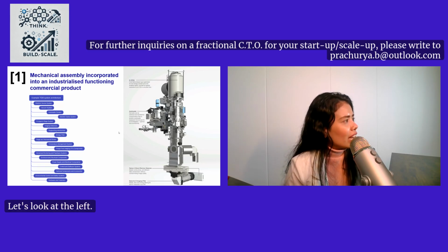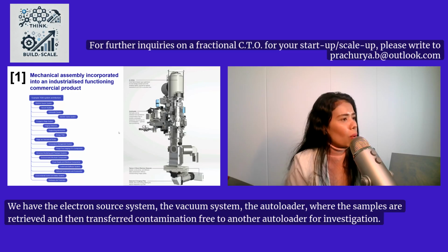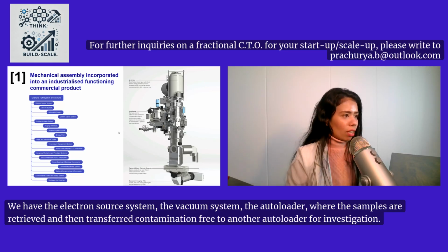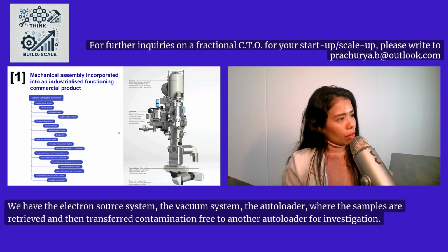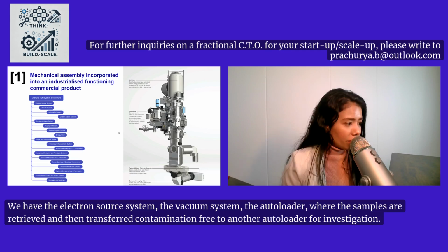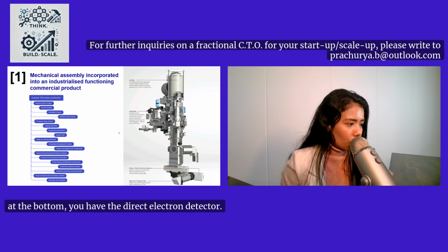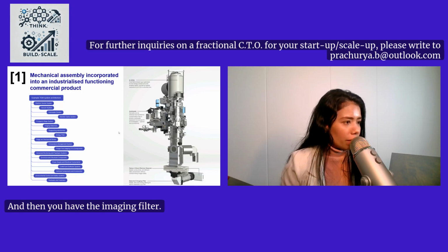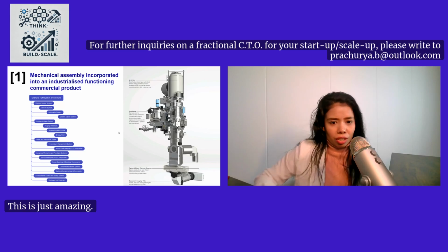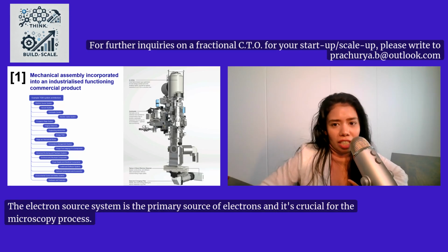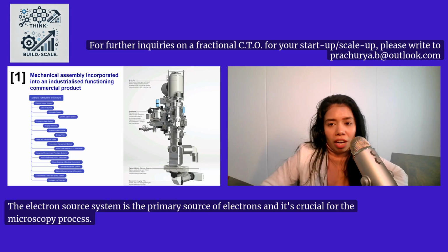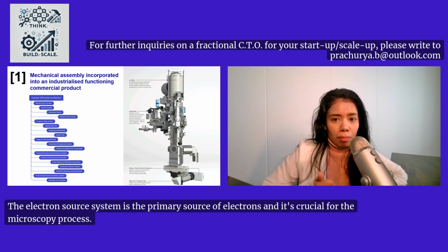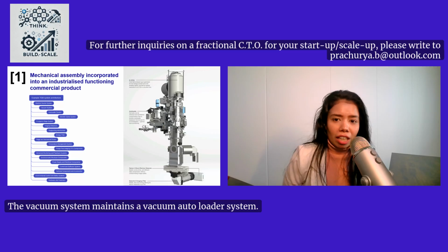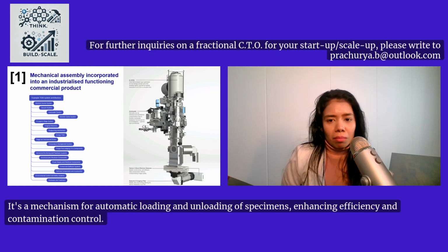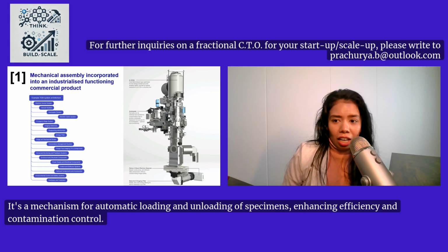Let's look at the left. We have the electron source system, the vacuum system, the autoloader where the samples are retrieved and then transferred contamination free to another autoloader for investigation. At the bottom, you have the direct electron detector, and then you have the imaging filter. This is just amazing. This is just wonderful. The electron source system is the primary source of electrons, and it's crucial for the microscopy process. The vacuum system maintains a vacuum. The autoloader system is a mechanism for automatic loading and unloading of specimens, enhancing efficiency and contamination control.